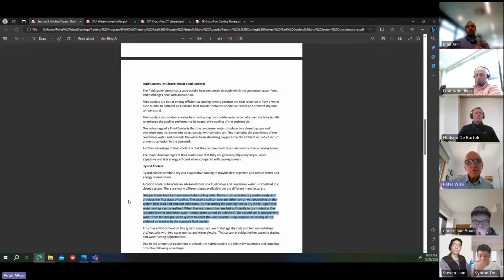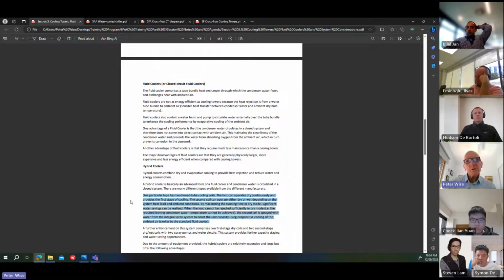One particular type has two finned tube cooling coils. In the fluid cooler, it's not a finned tube, it's just a tube bundle, so there are no fins. But in the hybrid, this particular type has finned tube cooling coils, so you're getting a greater heat transfer surface area. The first coil operates dry continuously and provides the first stage of cooling. So when the ambient conditions are okay for dry cooling to achieve the required condenser water temperature, the first stage will operate. The second stage coil can operate either dry or wet, depending on the system heat load and ambient conditions. So the first coil will always stay dry. The second coil can be wet by circulating water through it, in the same way as a fluid cooler does.